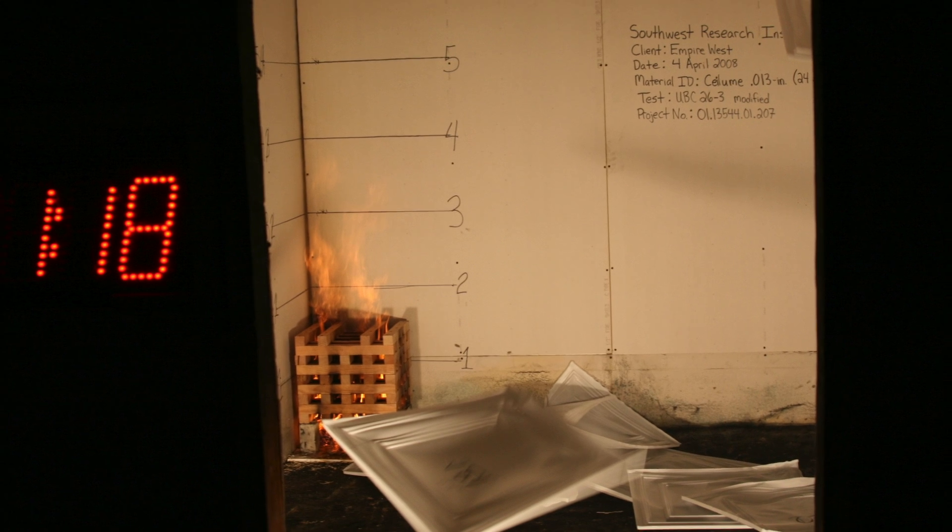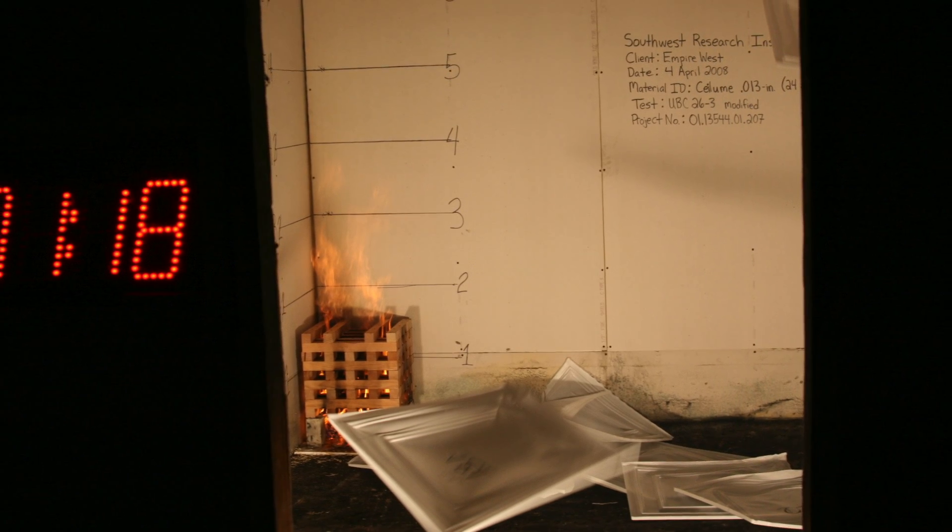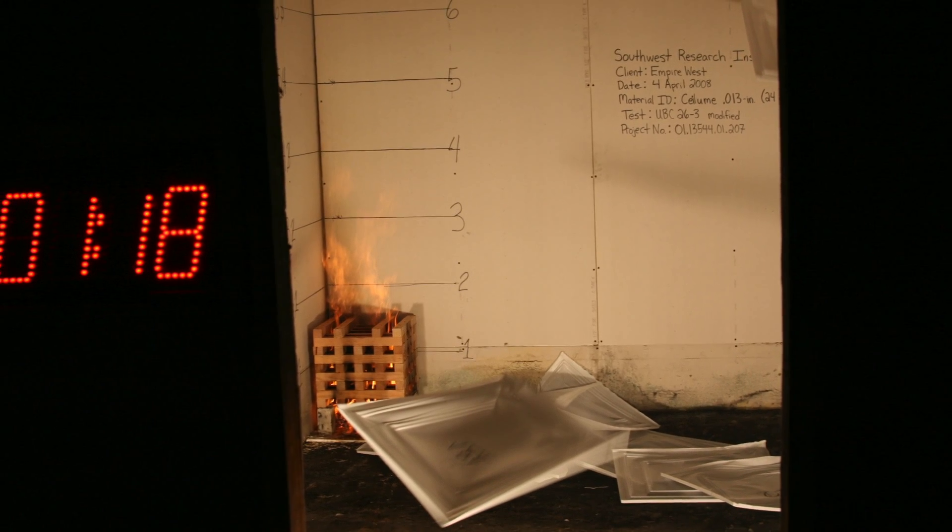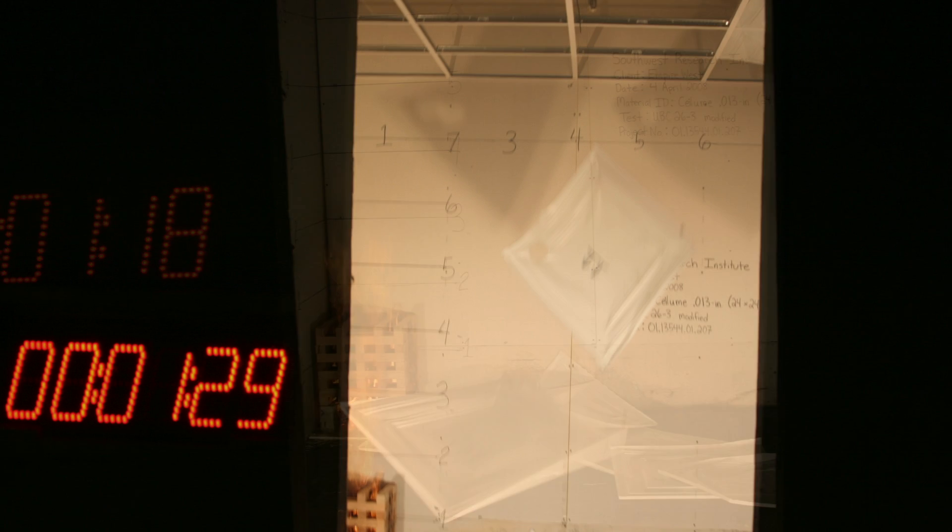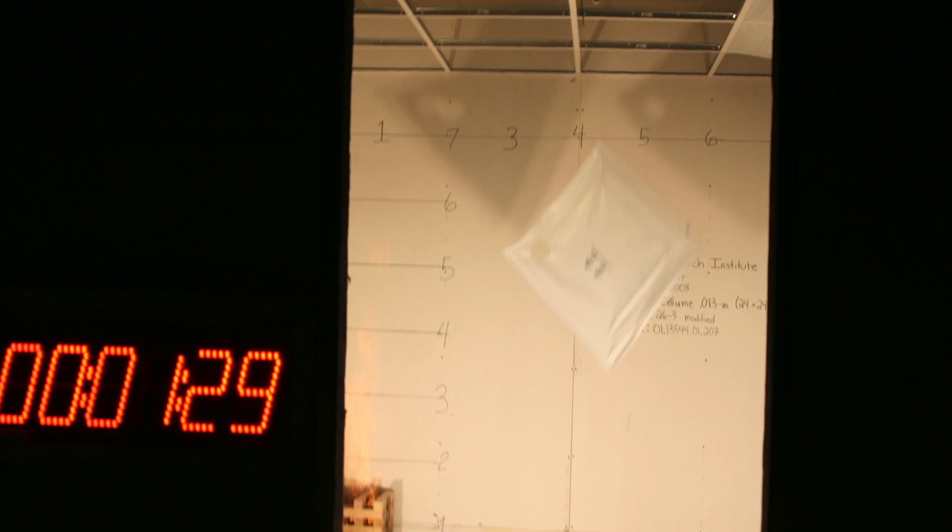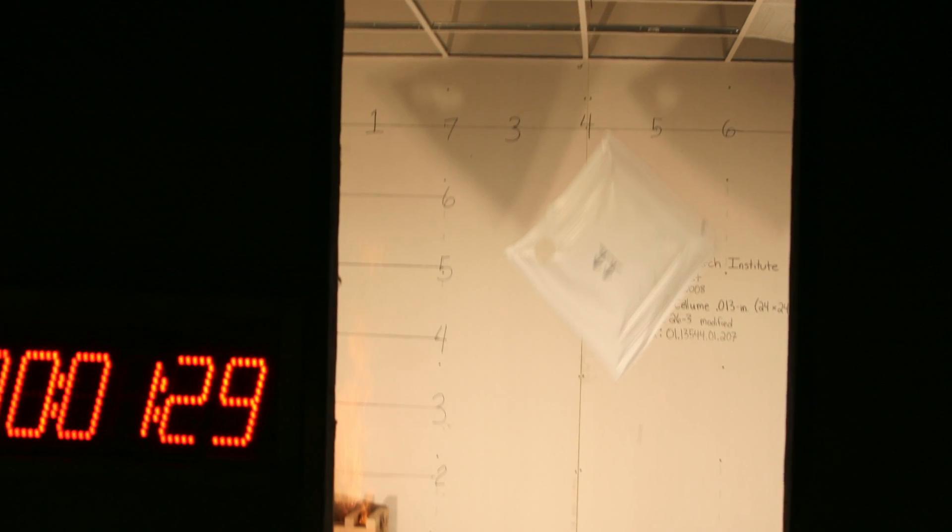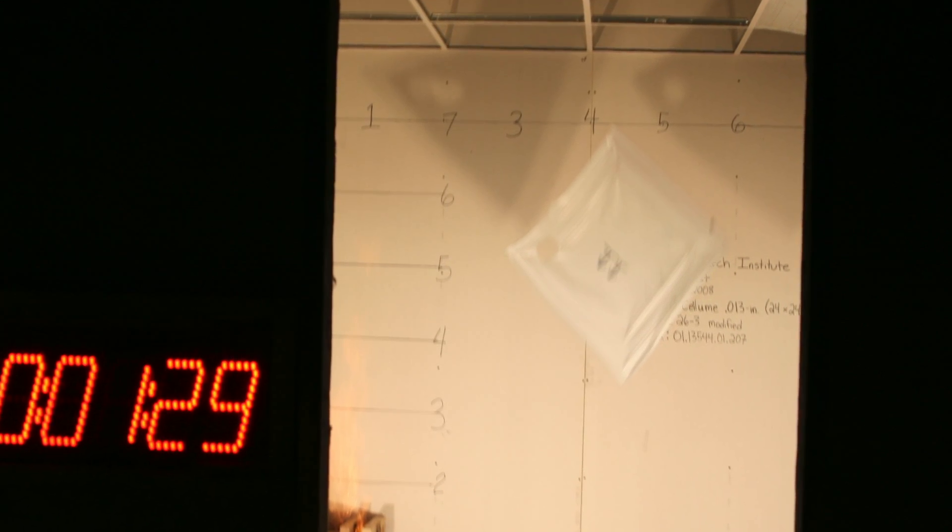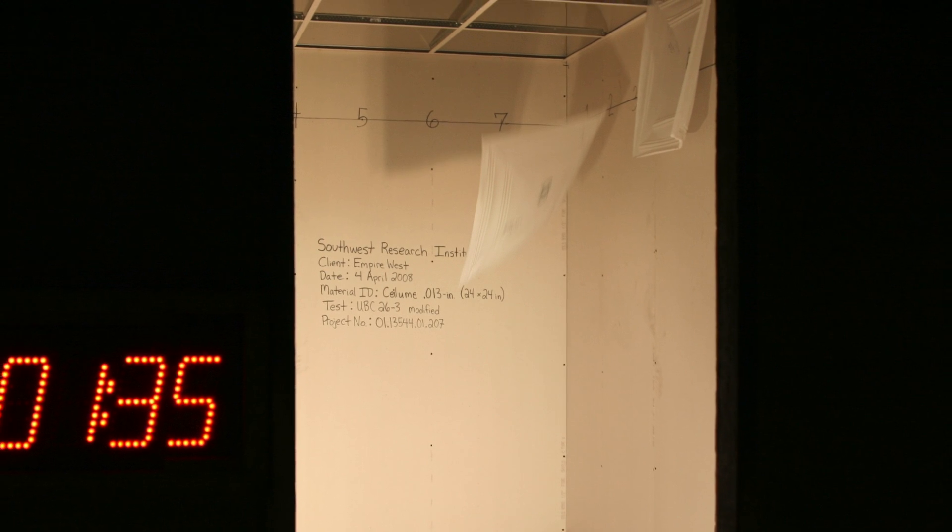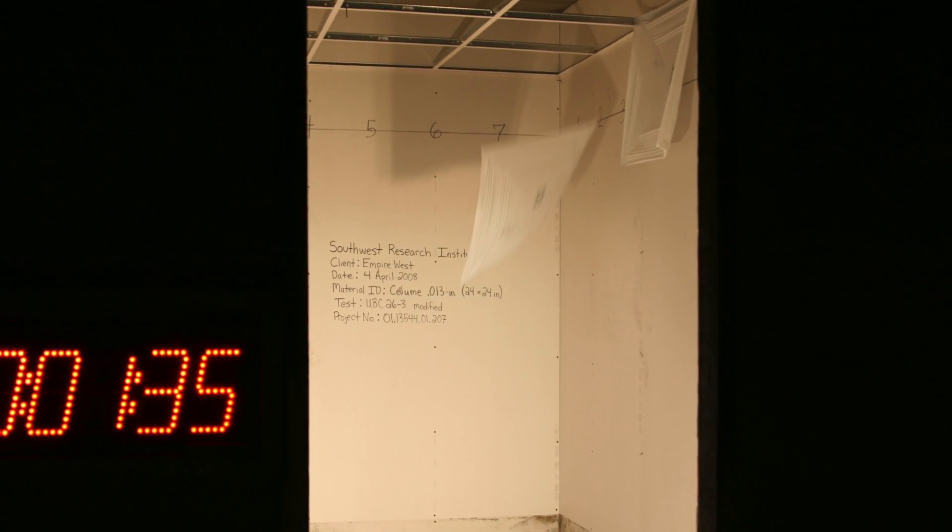Because of their material composition and very low mass, panels do not contribute significant fuel to support combustion. They simply fall to the floor and cool quickly, leaving the grid empty so the sprinklers can do their job.